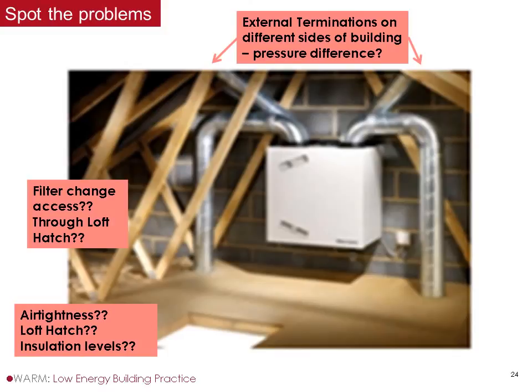Here's a bit of a subtle one. The external terminations are on different sides of the building, so when the wind's blowing strongly in one direction or the other, you'll get quite a big pressure difference across it, which will alter the balance of the unit, the supply and demand. I personally prefer them to be on the same side. You've got to have them a certain distance apart to avoid short-circuiting, but I'm not so keen on that arrangement.